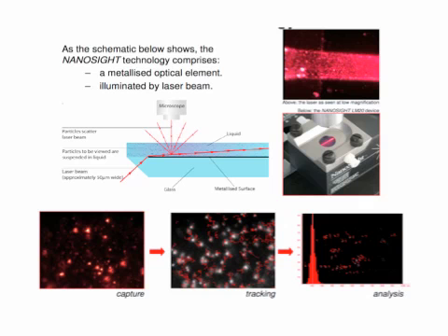So this is some of the toys we have. Yeah, so the laser beam comes in. Here under the microscope eye, it scatters light. So you see lots and lots of particles that scatter light, and they're submicron in size. And what you do, you basically make a video clip, and you see how it buzzes around. And then you have tracking software that at time 0 selects all these dots, and then just follows how it moves. And it uses then the Stokes-Einstein theory to calculate the size distribution.